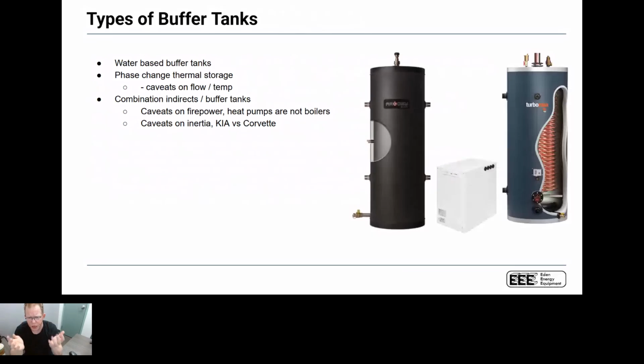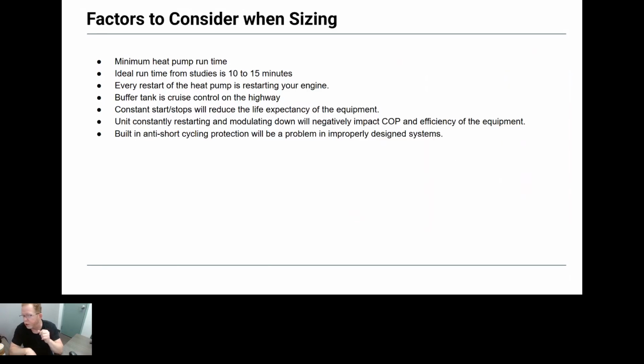Now, as far as types of buffer tanks, I've grabbed 3. There's water-based buffer tanks. There's obviously phase change thermal storage buffer tanks. Anybody who knows anything about me knows I like phase change. Obviously, when you're using phase change, it's not a true buffer tank. It acts as a battery, so there are some caveats on flow there. And then the other thing that's really, really cool that I particularly like on these systems is combination indirects. So Heat-Flo makes a really good one. I believe it's called the One. Turbomax, which is a Quebec-based company, and Thermo 2000 make a really good one as well. So these are really creative ways that we can use buffer tanks as part of our systems.